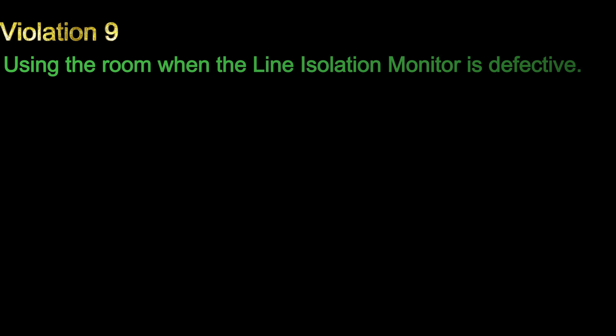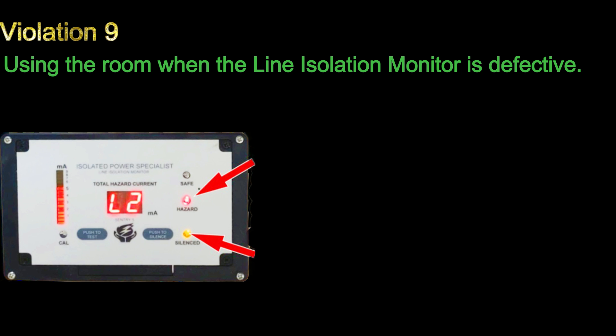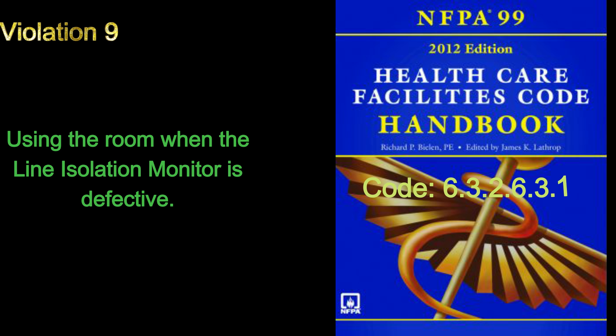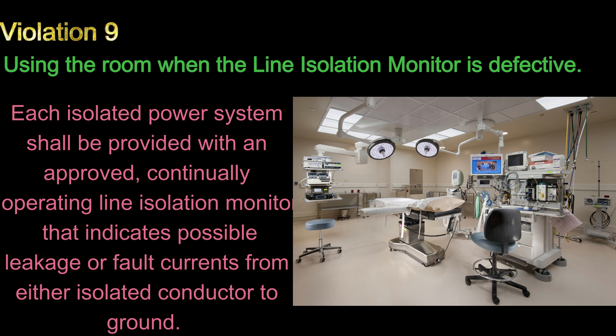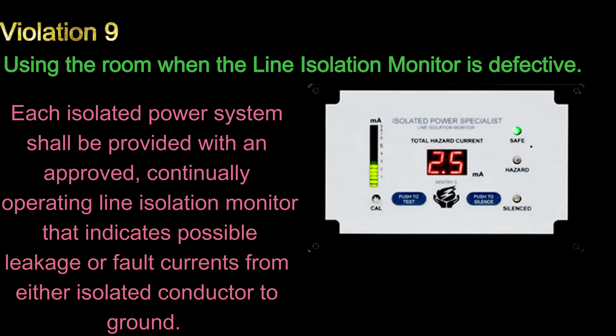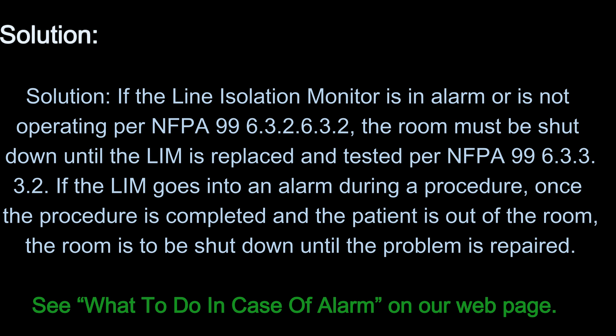Number 9: Using the room when the line isolation monitor is defective. Code 6.3.2.6.3.1 — each isolated power system shall be provided with an approved, continually operating line isolation monitor that indicates possible leakage or fault currents from either isolated conductor to ground. Solution: If the line isolation monitor is in alarm or is not operating per NFPA 99 6.3.2.6.3.2, the room must be shut down until the LIM is replaced and tested per NFPA 99 6.3.3.3.2. If the LIM goes into alarm during a procedure, once the procedure is completed and the patient is out of the room, the room is to be shut down until the problem is repaired.